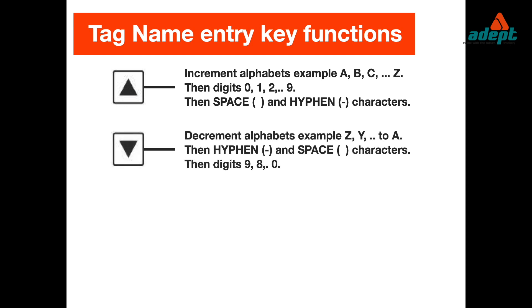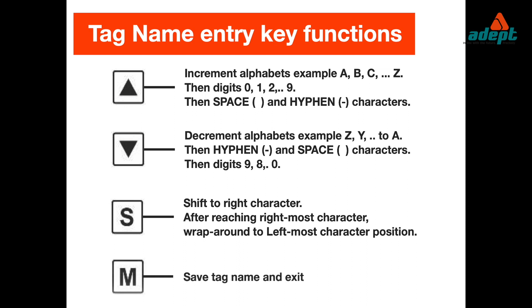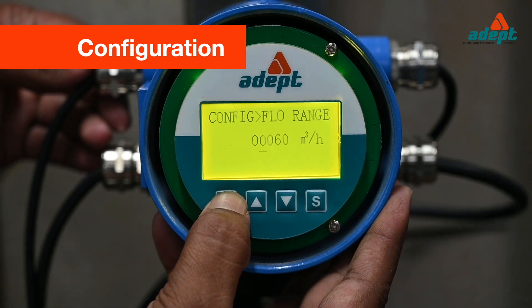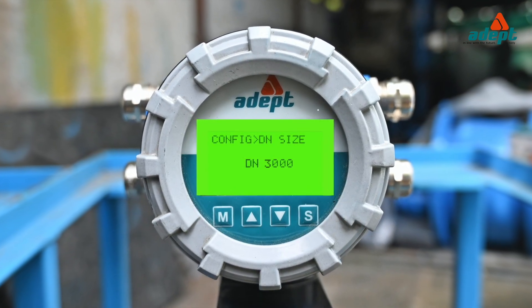Down arrow key decrements alphabets, for example Z, Y up to A, then hyphen and space characters, then digits 9, 8 up to 0. S key shifts to the right character; after reaching the rightmost character it wraps around to the leftmost character position. M key saves the tag name and exits configuration. Set pipe size as required, DN10 to DN3000.